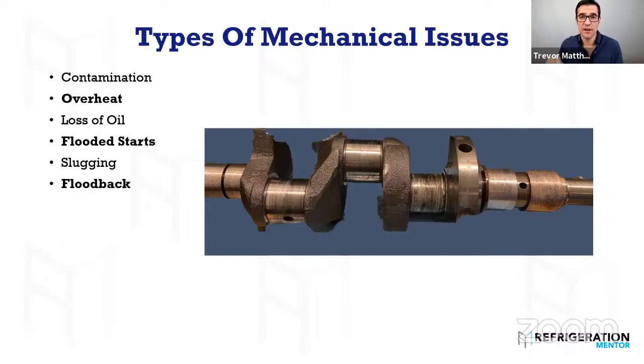You check at the compressor, and if you have 0 degrees superheat, that's floodback. If you have 20 degrees or 11K, you know you have superheat there, so you know there's no liquid happening. And then you need to understand the type of refrigerant you're using, because CO2 compressors are going to have different superheats, mandatory, compared to a regular HFC, HFO compressor. So you need to look this up in the compressor manufacturer guides. If it's Copeland, Bitzer, or Danfoss, they all write good manuals for their compressors. You need to dive into those ones.